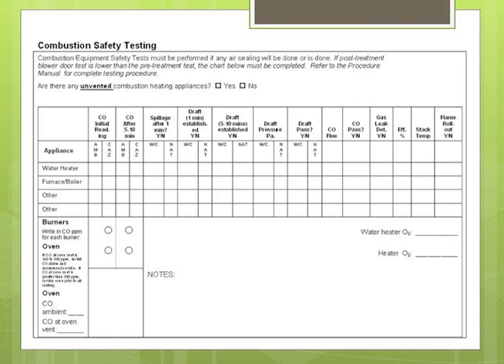We take an initial carbon monoxide reading — ambient, which is anywhere in the house, and CAZ, which is in the Combustion Appliance Zone. Then, after five to ten minutes of having the appliance on, we check for spillage. We'd take smoke and put it around that cap on the hot water heater to see if the smoke went into the flue or was pushed out, to determine whether there were pressure issues preventing that flue from working properly.